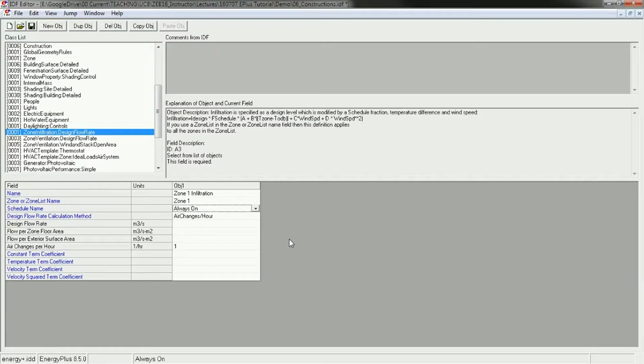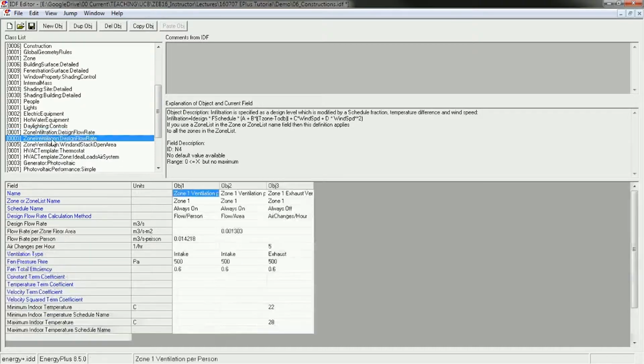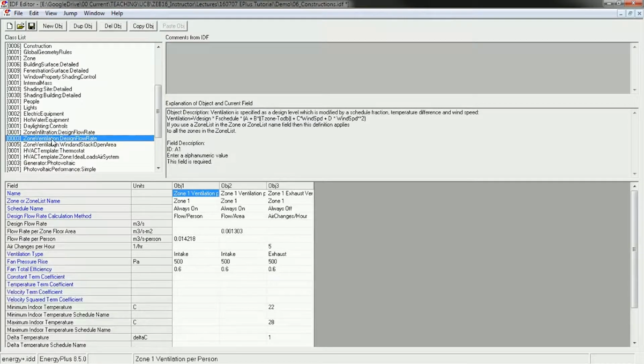This building, Worcester Hall, has very leaky envelopes. You can feel it, the air infiltrating in, particularly through the windows. And so I've set here an air change rate of one air change per hour. That's pretty leaky. And so we're getting a lot of unwanted air in, both cold and hot, and you'll see dramatic impacts.